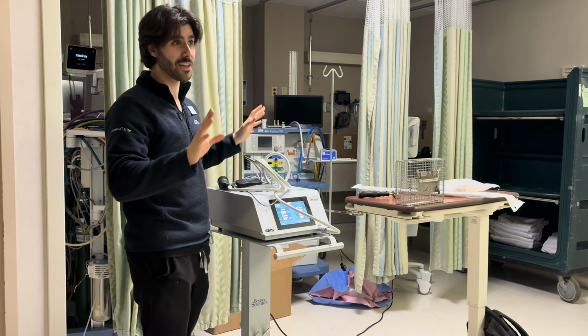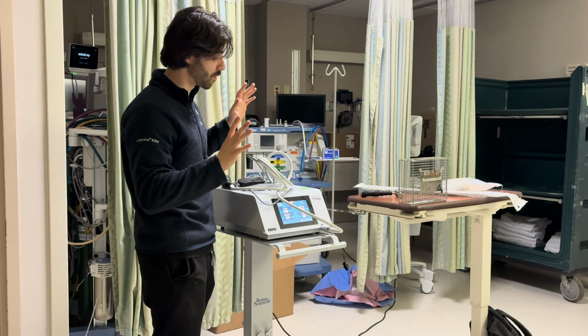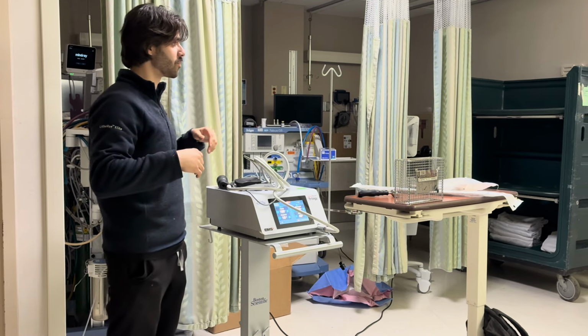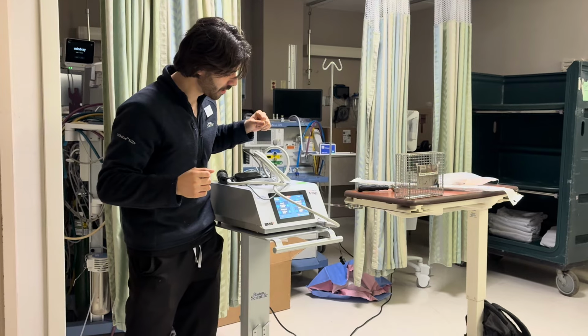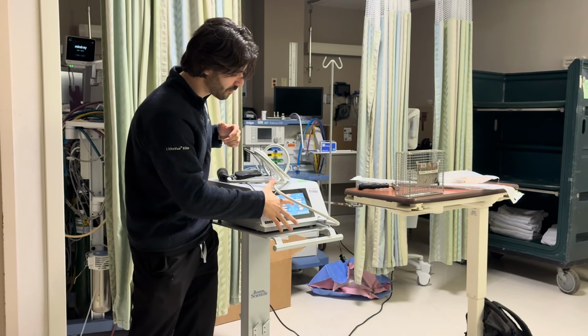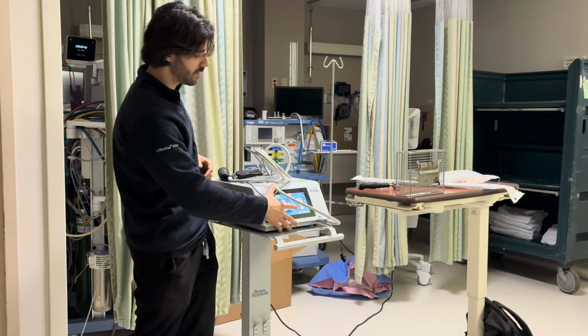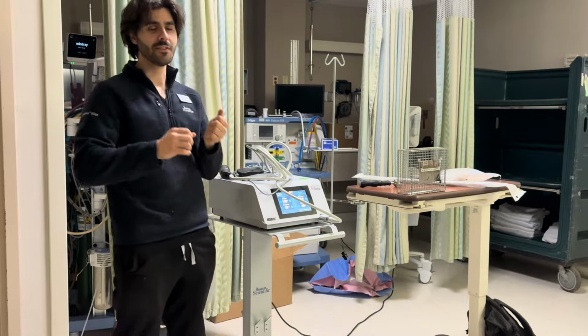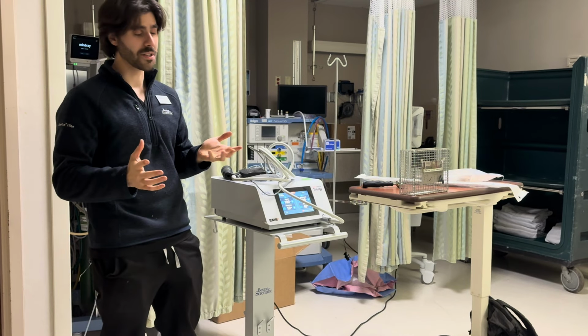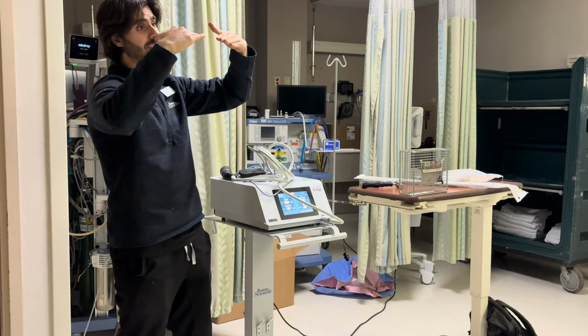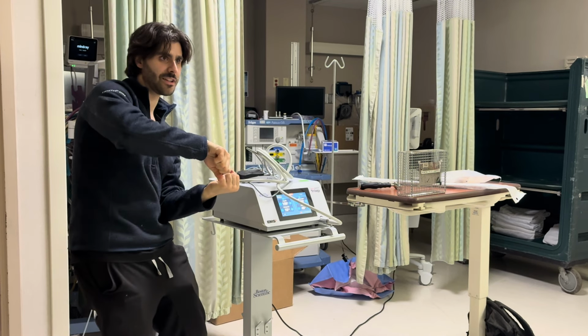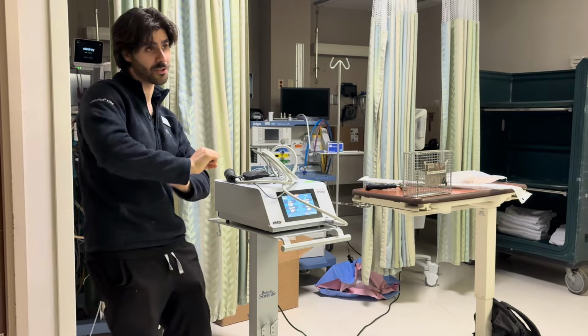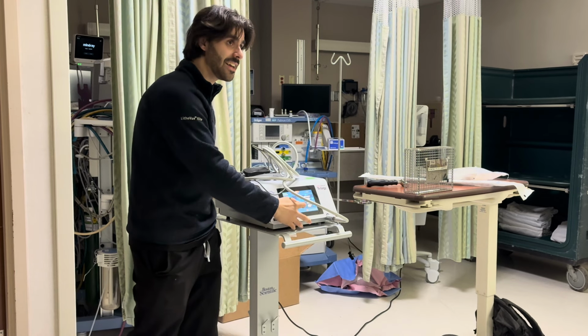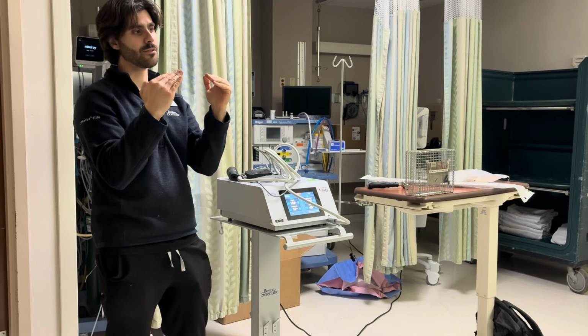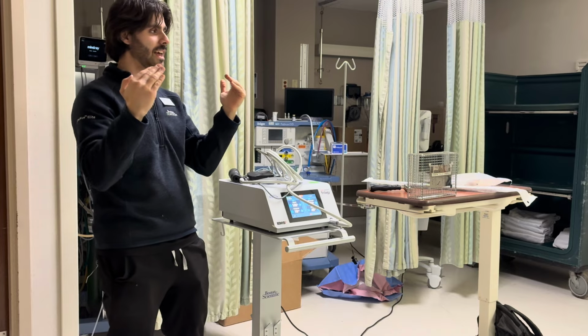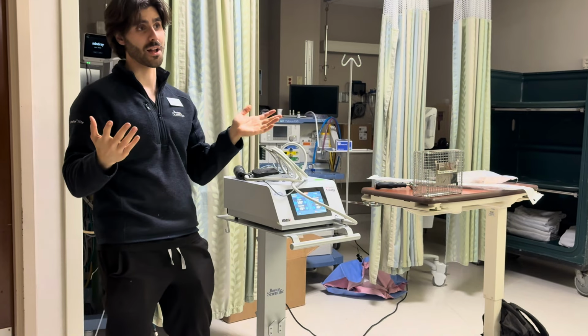Dr. McRae is usually very conservative with the settings when it comes to the suction, so you shouldn't need to worry about that. But aside from that, there's this little bar right here. Throughout the case, this bar should always be on the green. If it's ever on the red, sometimes it's normal because you have to. That just means that the probe is being bent. Sometimes you're in a very difficult place in the kidney, so you have to bend it a little bit. But if it stays on the red for too long, then you actually risk damaging the probe, and at some point the probe will stop working.